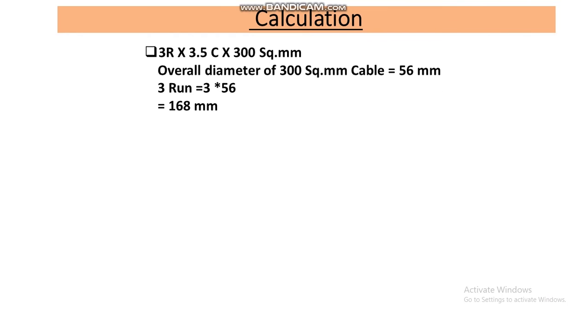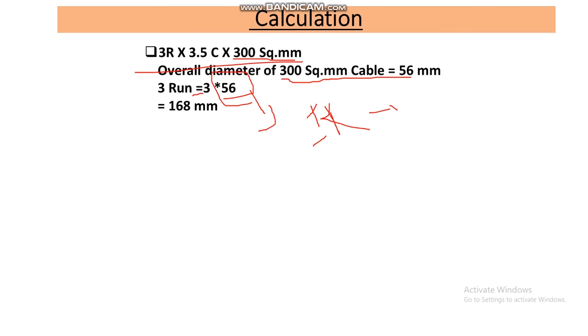So for three runs of 3.5-core 300mm² cable, the overall diameter is 3 × 56mm = 168mm. The overall diameter for the three runs of 300mm² cable is 168mm.